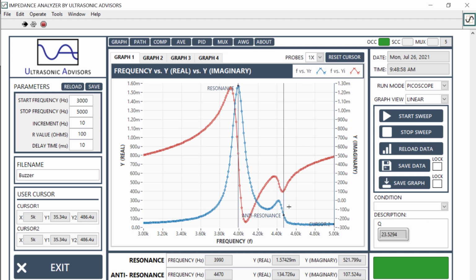One of the reasons why we do have more spurious modes with bending transducers is because their assembly relies more heavily and is affected more so by concentricity. So any difference in concentricity, which clearly, the disc in front of me is not concentric. The piezo is not concentrically bonded with the brass disc shim, just due to this manufacturing use case.